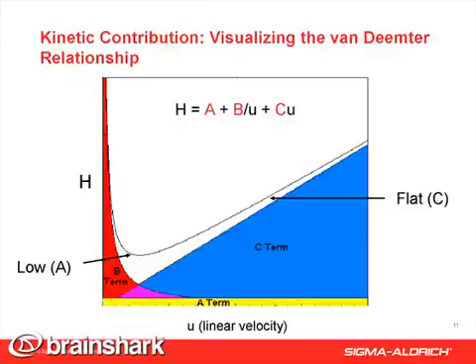The A term is this yellow portion that influences the minimum attainable H. The primary contributors to the A term are how well packed the column is and the particle size distribution. And both of these are exactly what our jobs are about.